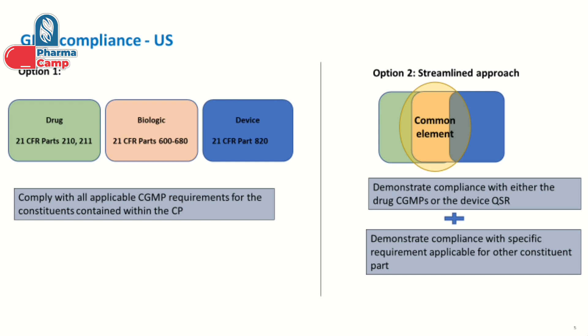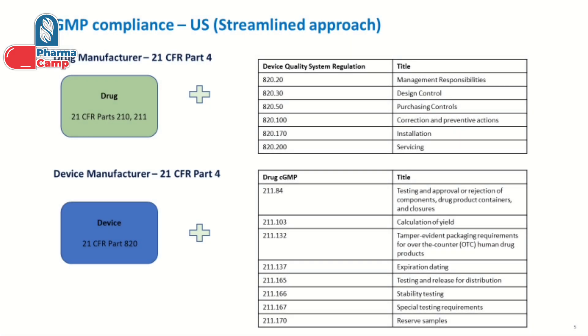Let's understand this with an example. If the primary mode of action of your product is drug, the manufacturer can choose to comply with the drug GMP requirements and in addition follow only the relevant parts of the device GMP. Similarly, if the primary mode of action is that of a device, the manufacturer can comply with the device GMP requirements mentioned in 21 CFR Part 820, and in addition follow only the relevant parts of the drug GMP. This makes the job much easier and streamlined — that's the purpose of this new approach.